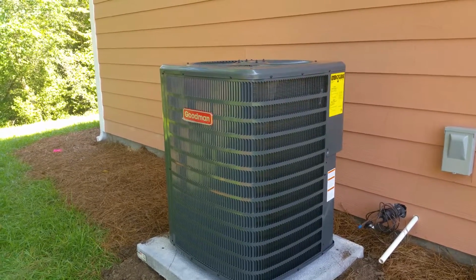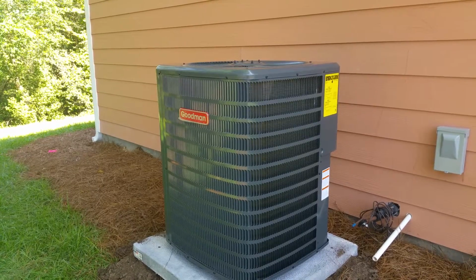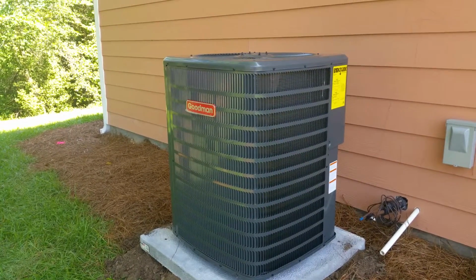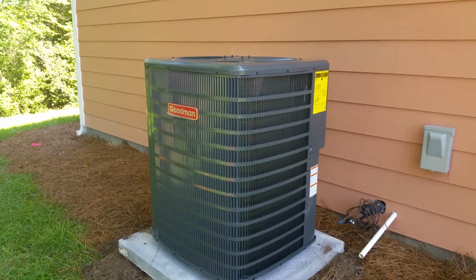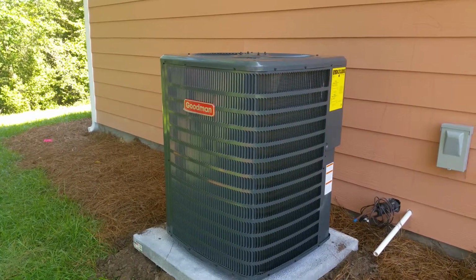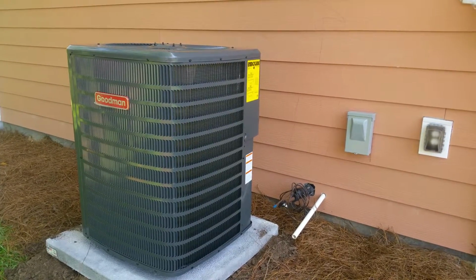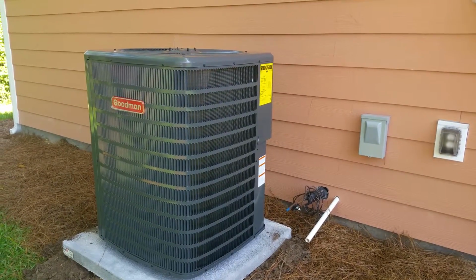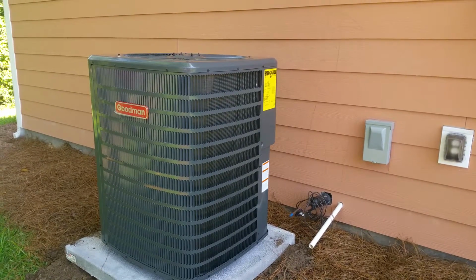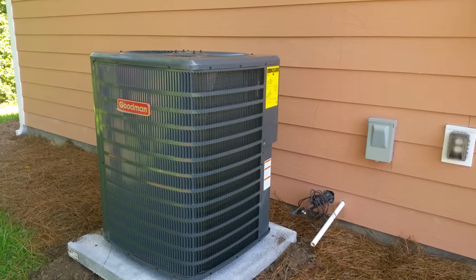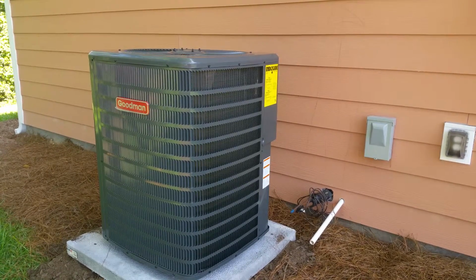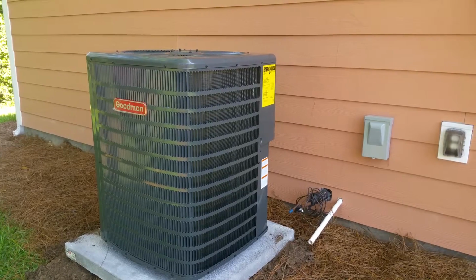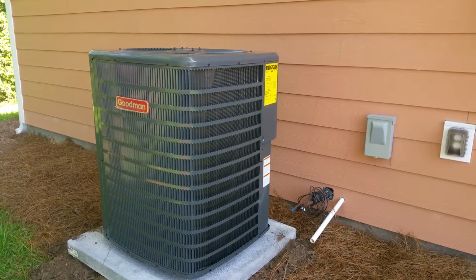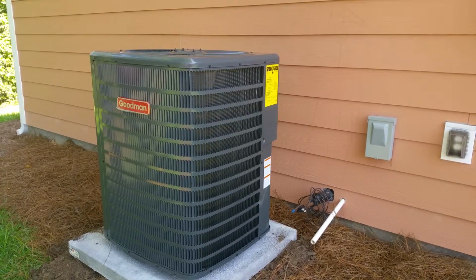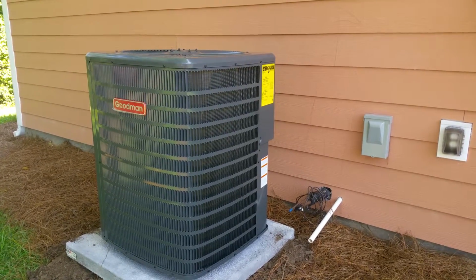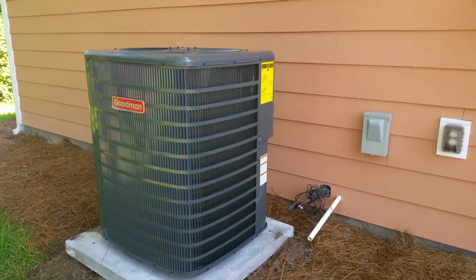Okay, and for this size house, is this an overkill? No, now we have to, by the standards, we have to do a heat load, and they size it for our design temperatures here in Myrtle Beach. But it's basically designed that on a 100-degree day like today, it should cool it down to like 73, 74 degrees. So you basically size it on the extreme load. And with the heating, we have the air handler upstairs with a 10 kW strip. And that's designed that if we have about a 12 or 13 degree, we only get a couple of hours a year, that we should maintain 70 degrees inside the house.